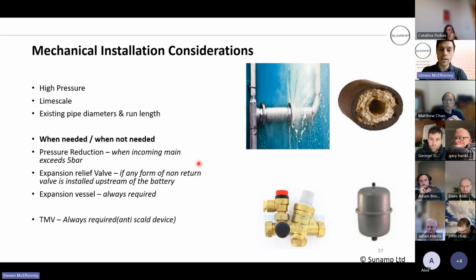System components from ourselves: a pressure reducing valve when the incoming mains pressure is going to exceed 5 bar, or you think it's at risk of doing that. So you fit a pressure reducing valve. Expansion relief between, I would say, 6 bar. We do say between 6 and 10, but if you've got a pressure reducing valve set to 5 and it fails, you're going to allow the pressure to go up to 10 bar before it starts relieving. I'd want that relieving much faster than that myself. So yeah, expansion vessel, 0.5 litre, always required. And the TMV is always required as well. It's an anti-scald device primarily, but as we talked about earlier, you can increase your capacity.